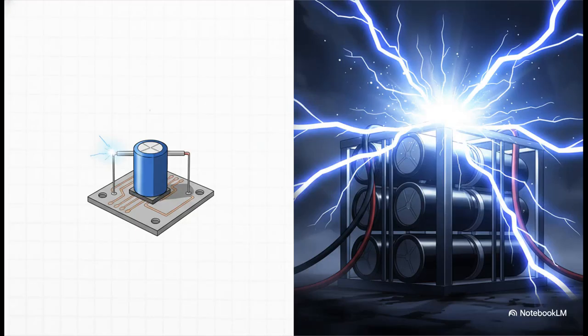So how is this possible? Well, it's just physics, but physics with deadly consequences. High-voltage cables act like capacitors, they store energy. Now look at this formula: the really important part is that the stored energy is proportional to the voltage squared. Let me say that again, the voltage is squared. That means if you double the voltage, you don't just get double the stored energy, you get 4 times the stored energy. So now imagine going from 440 volts to 6,600. The amount of invisible, lethal energy just sitting there in that dead cable is astronomical. It's a silent threat you have to respect.